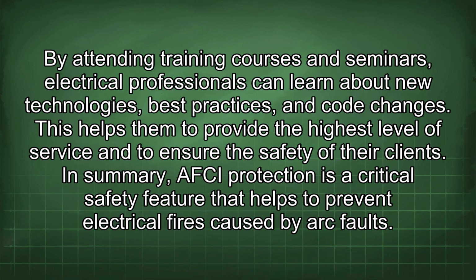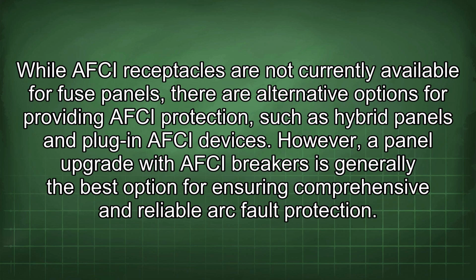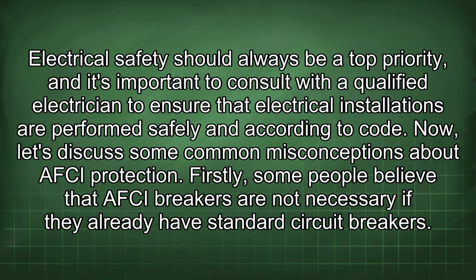In summary, AFCI protection is a critical safety feature that helps to prevent electrical fires caused by arc faults. While AFCI receptacles are not currently available for fuse panels, there are alternative options for providing AFCI protection, such as hybrid panels and plug-in AFCI devices. However, a panel upgrade with AFCI breakers is generally the best option for ensuring comprehensive and reliable arc fault protection. Electrical safety should always be a top priority, and it's important to consult with a qualified electrician to ensure that electrical installations are performed safely and according to code.